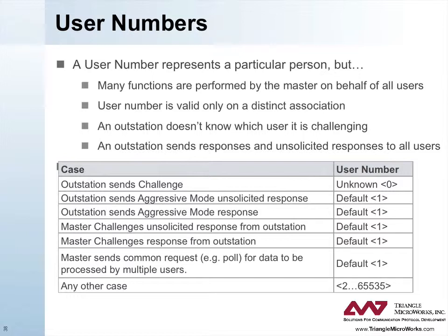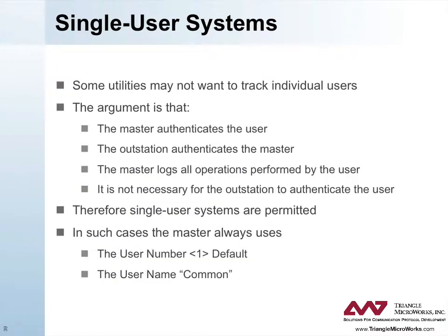The outstation doesn't know which user it is challenging. Some utilities may not want to track individual users. Their argument is that the master authenticates the user, the outstation authenticates the master, the master logs all operations performed by the user, and so it's not necessary for the outstation to authenticate the user. Therefore, single-user systems are permitted. In such cases, the master always uses user number one — default — and the username common.